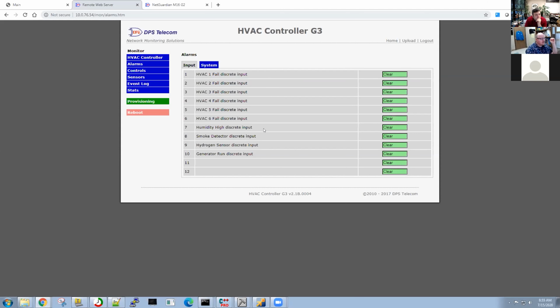Alarms is going to basically give us some feedback from other kinds of inputs that are more discrete in nature. So on the 66 block that we ship out, there's a front panel that has labeled all of the contacts that we'll need to maintain here: HVAC 1 failing, HVAC 2 failing, HVAC 3 failing. So those are all feedback kinds of things from the HVAC unit itself.